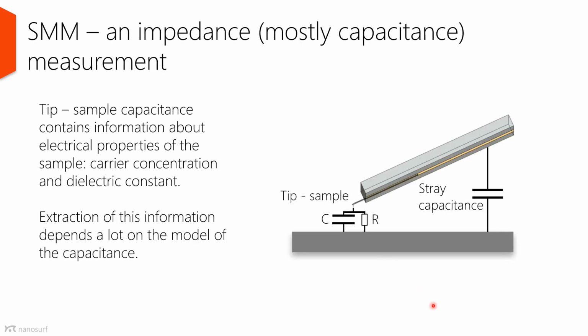On the previous slide, I spoke about measuring the material parameters, which is the ultimate goal of the measurement. Now let's take a step back and get a little better understanding of the instrumentation. On the instrument level, what the electronics is really measuring is the tip sample impedance. In that sense, one might call it a microwave impedance microscopy. And the impedance is essentially a combination of the capacitance and the resistance between the tip and the sample. And it is through the measurement of these two we can extract the electrical properties of the sample.